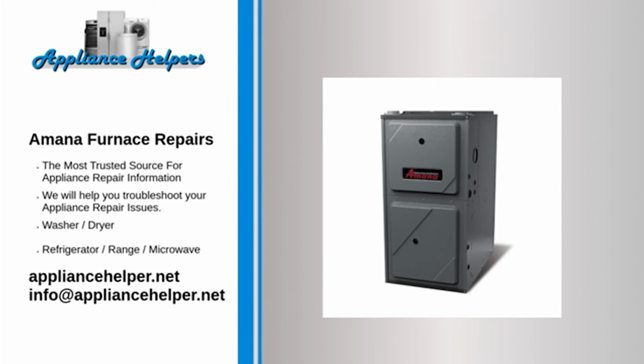Amana furnace blower runs all the time. The control board has relays that regulate the voltage to each component in the furnace. If the relay that controls the blower motor fails while it is closed, it will send continuous voltage to the blower motor, causing the motor to run continuously. If the control board is at fault, replace it.